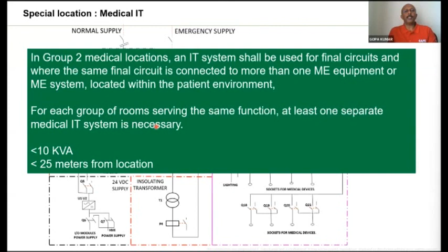But of course, in a medical location, there is an OT panel. People call it an OT panel. The OT panel is implemented in some of the hospitals, but don't think that this is the only recommendation. No, as I said in the previous slide, there are 3 different things. The OT panel is required, plus you need to have supplementary equipotential bonding, meaning the measures to reduce the touch voltage, maximum 25 volt is necessary, because a hospital is a wet location. Also, this location requires additional tests, in the sense there are 10 tests specified in IS 732.